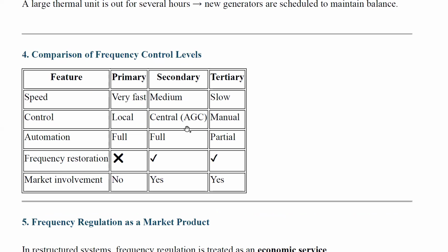Now a comparison of primary control, secondary control, and tertiary frequency control. In speed, primary control is very fast, secondary control is medium, and tertiary control is slow. Control-wise, primary control is local, secondary control is central, that means AGC, and tertiary control is manual, so you need to switch on manually. Automation: primary control is full, secondary control is also full, tertiary control is partial. Frequency restoration: primary control does not restore, because it only withstands the frequency change, but secondary control has frequency restoration, and tertiary control also has it.